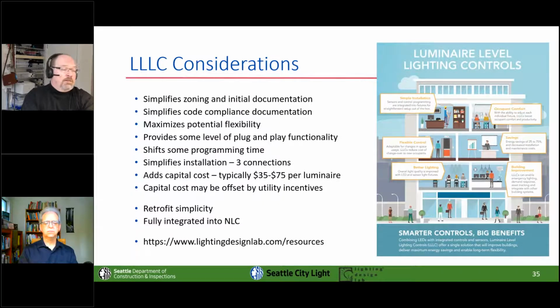A couple things about them: they simplify zoning and documentation, because they're all individual zones, so you don't have to think about that beforehand. They simplify code compliance documentation, because they automatically comply—you check a box in most jurisdictions. They maximize flexibility and provide some plug and play functionality. If you're a lighting controls whiz, that's fantastic. If you're not, most of them come from the factory with a certain level of programming already inherent, so they'll get you to 80% of the savings you need right out of the box, even if nobody touches them again. We're not advocating that, but it's helpful if that's the case.